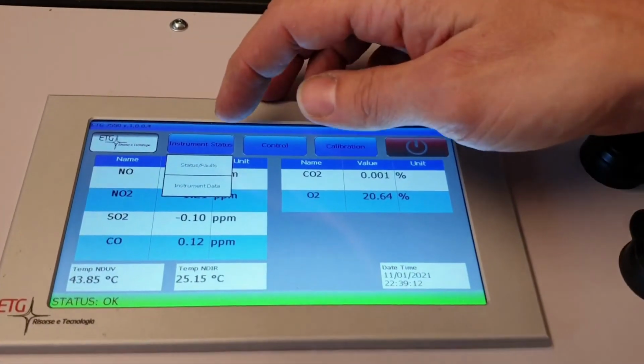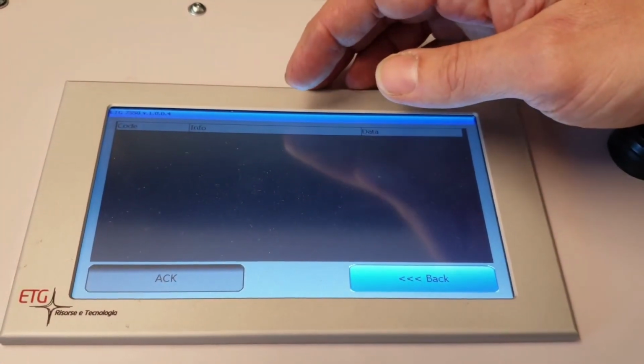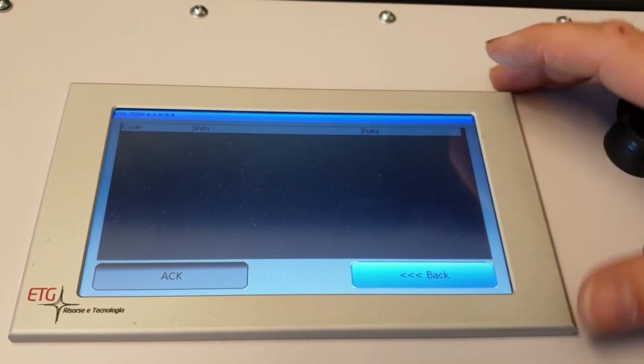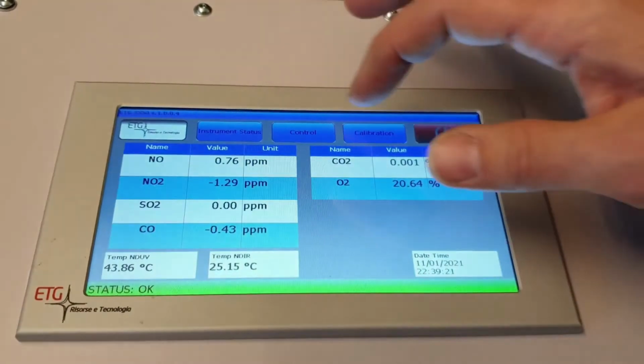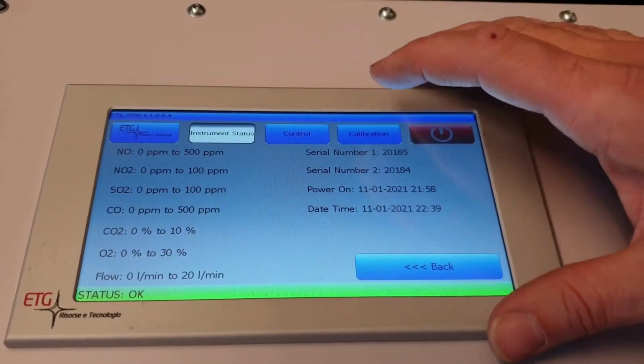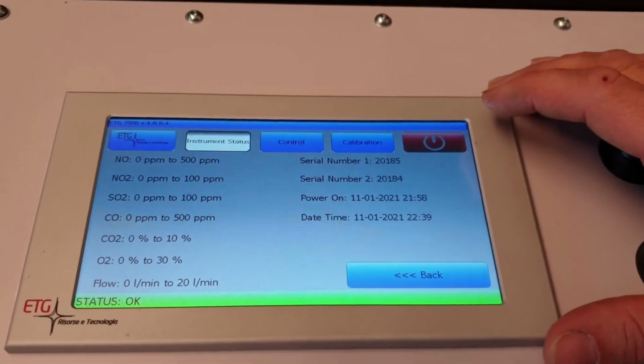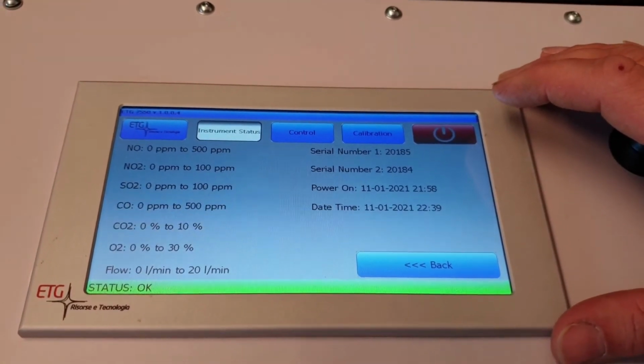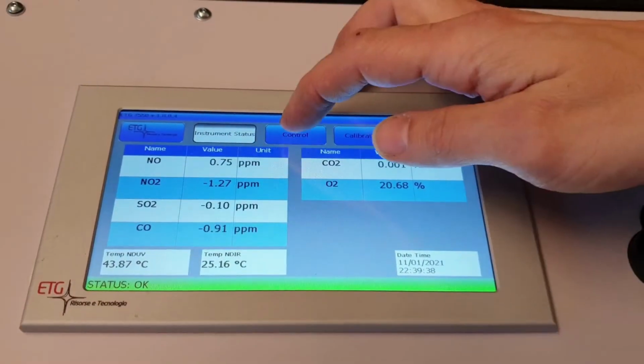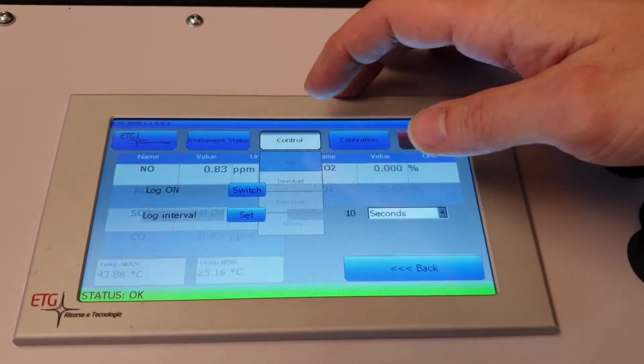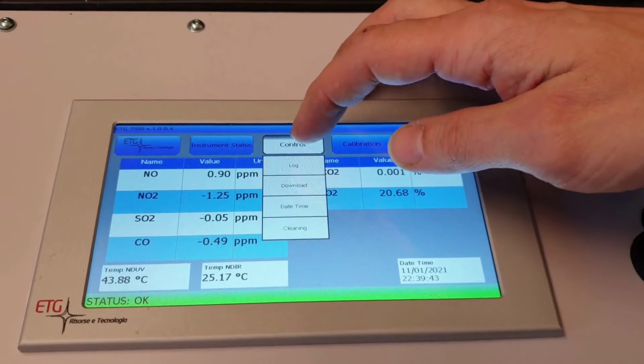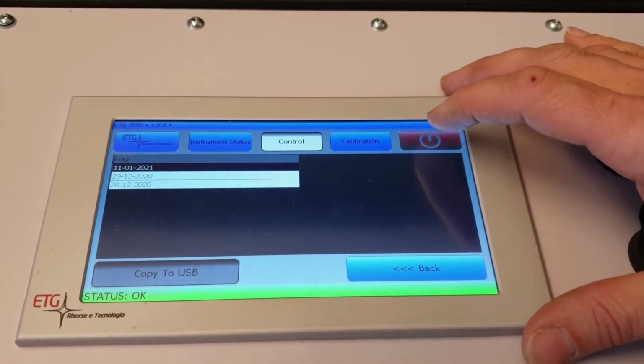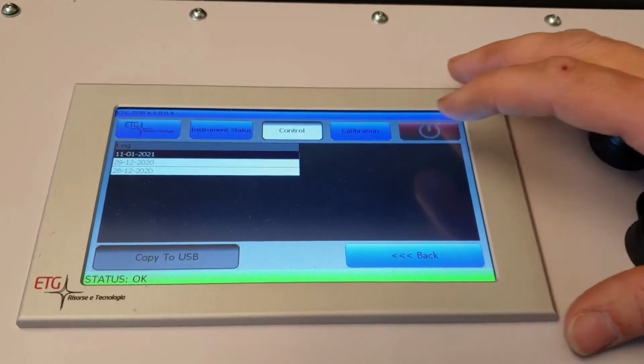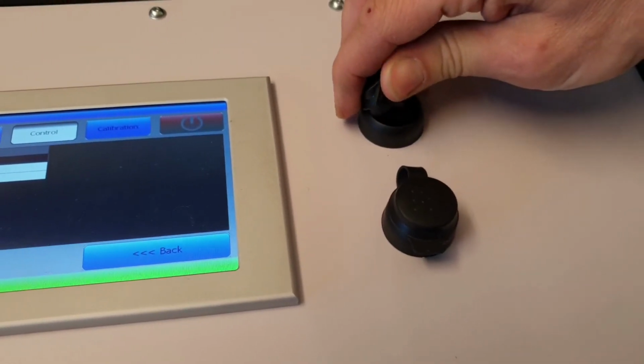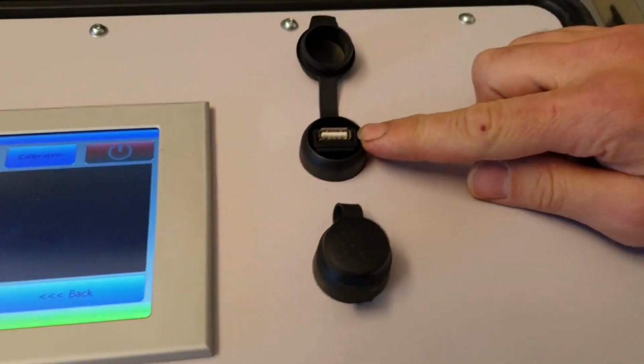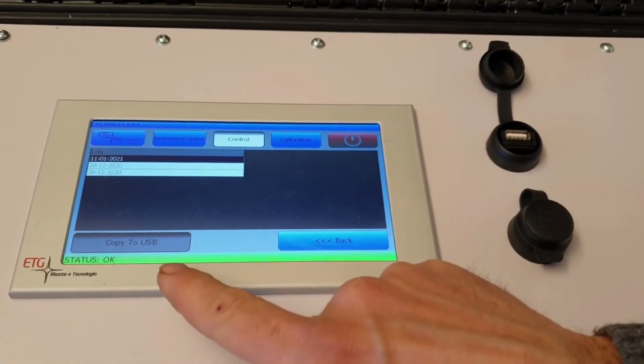On instrument status, you can see the status of the analyzer if there is some fault, and also instrument data, the gases that you can detect with this analyzer, and the range that is set. On the control menu, you can activate the log and download the data. You have to put a USB pen on this USB port, and then copy to USB.